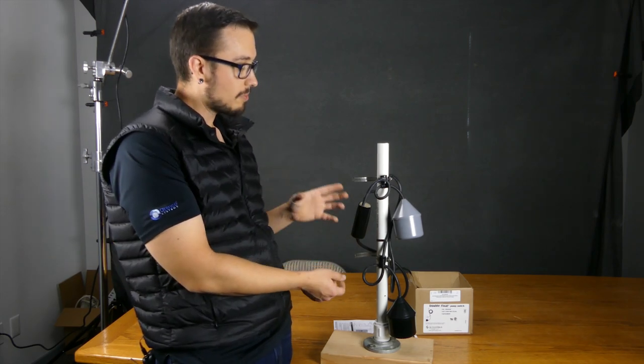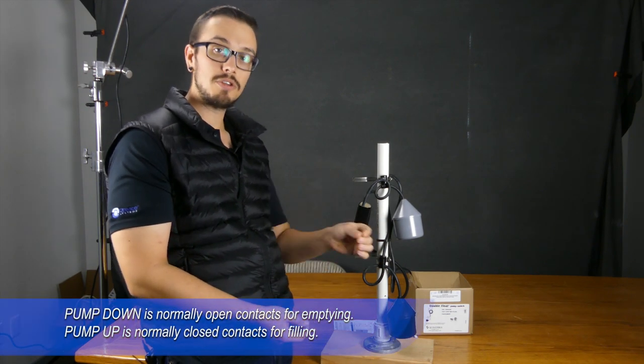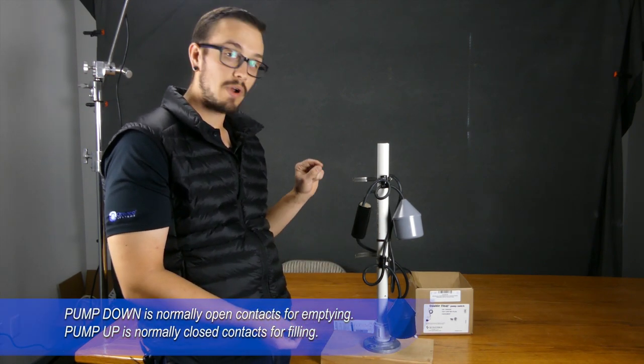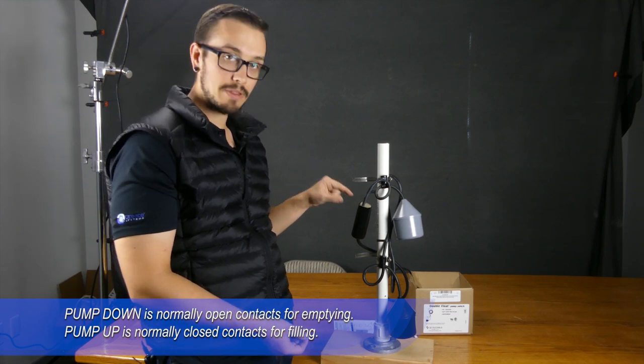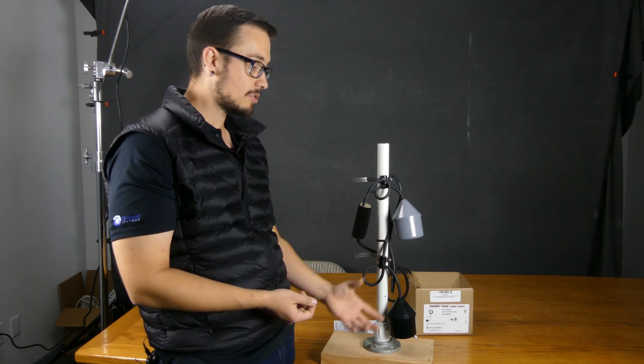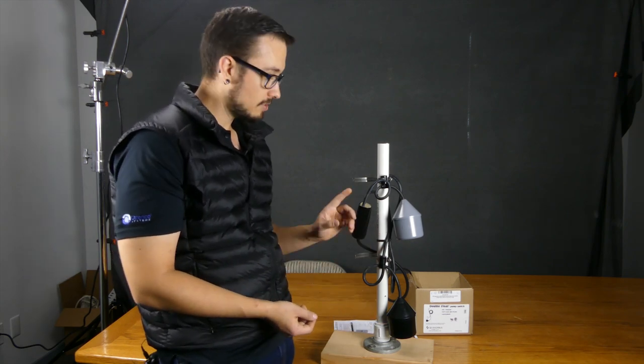That brings up another good point with these switches: you want to make sure you order the right configuration, pump up or pump down. But also just as critical is that you order the right voltage, because the way that this relay operates you have to have the right voltage. So you can't just grab a 120 volt configuration and use it in 230 volt and vice versa.